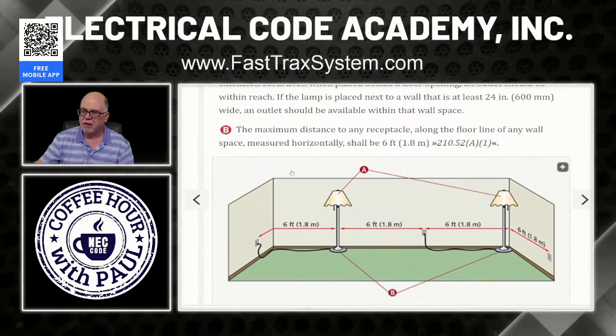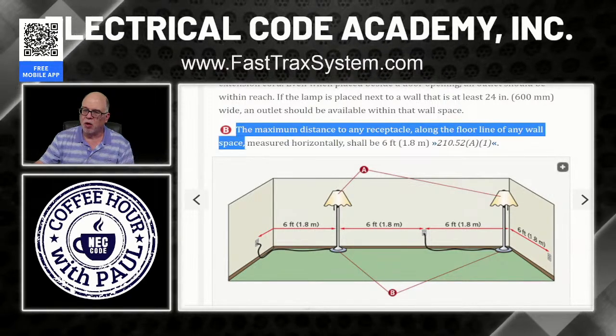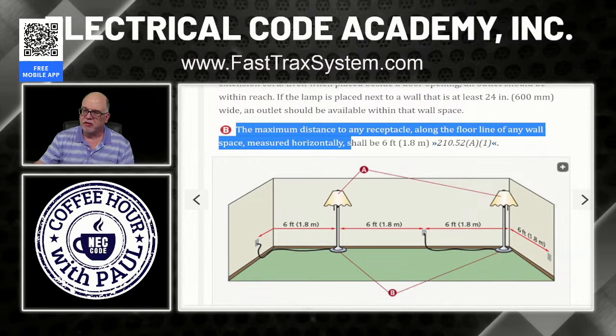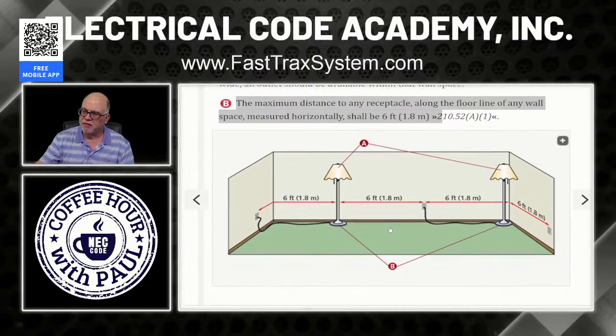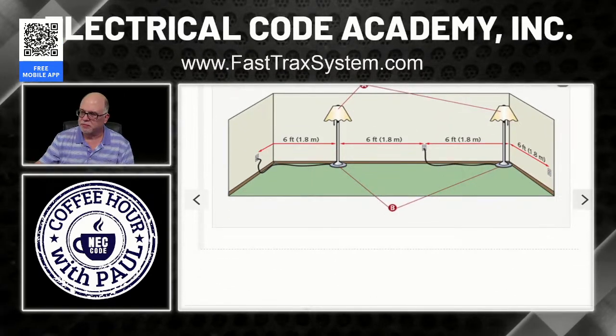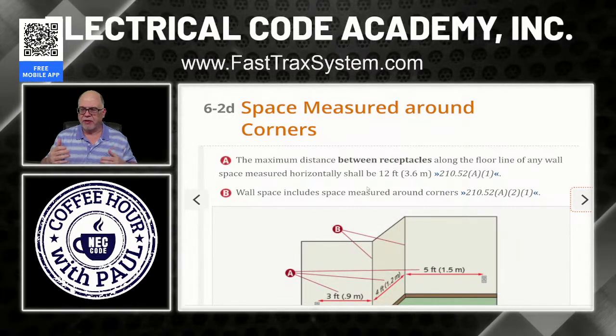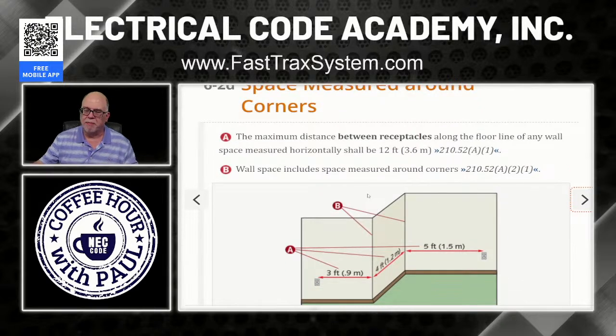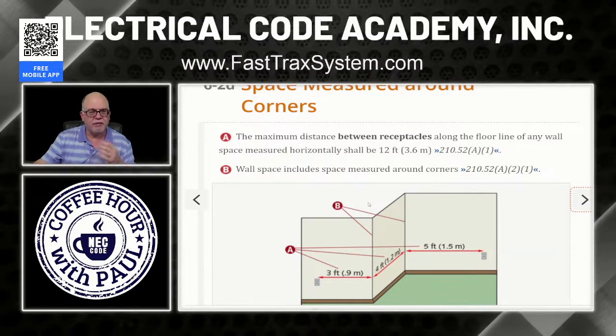Now, B, right here, is the maximum distance to any receptacle along the floor line of any wall space, measured horizontally, and it shall be 6 feet. So again, wherever I put this lamp with this 6 foot cord, I'm going to be within reach of a receptacle. Now, when you're measuring the wall line, this is where people sometimes will think, well, what about when the room is not perfectly square? Then you're going to follow the contours of the actual room.